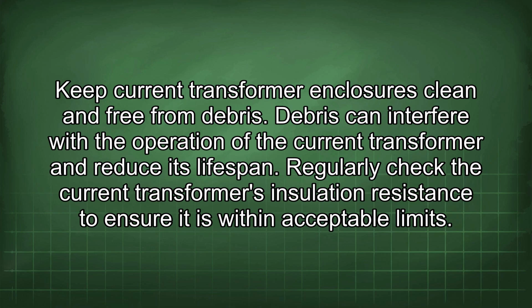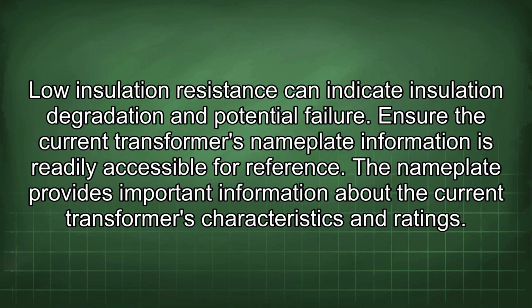Regularly check the current transformer's insulation resistance to ensure it is within acceptable limits. Low insulation resistance can indicate insulation degradation and potential failure. Ensure the current transformer's nameplate information is readily accessible for reference. The nameplate provides important information about the current transformer's characteristics and ratings.